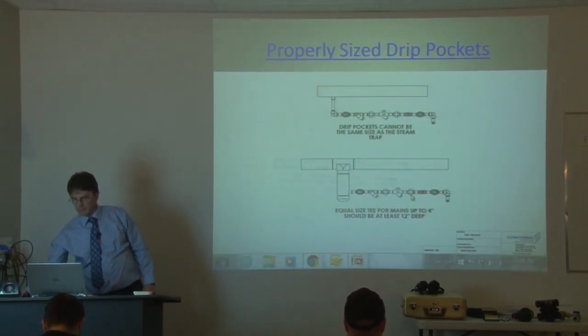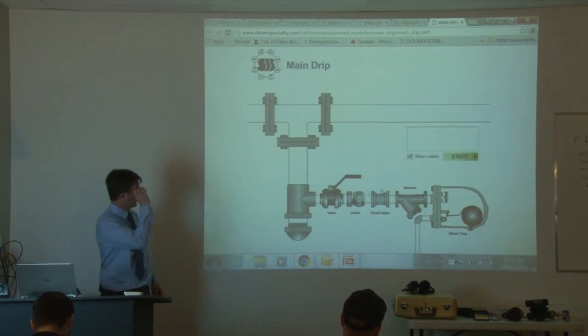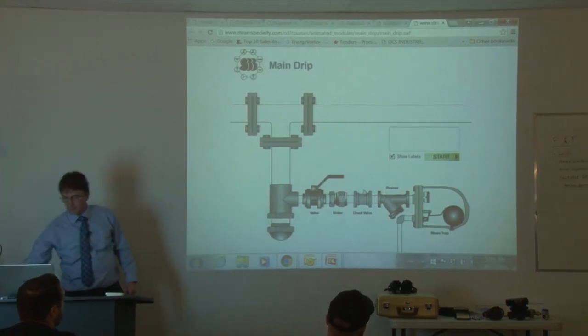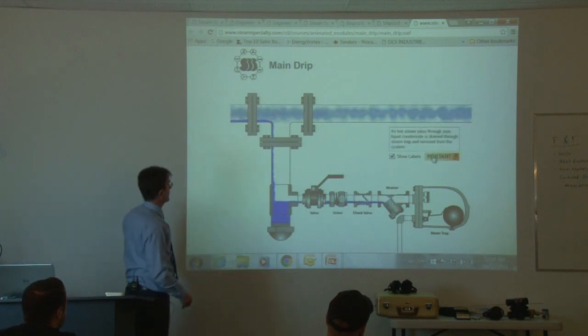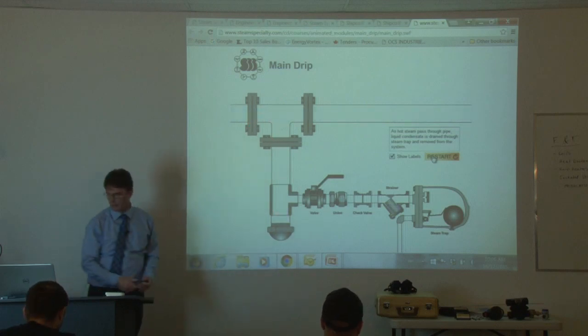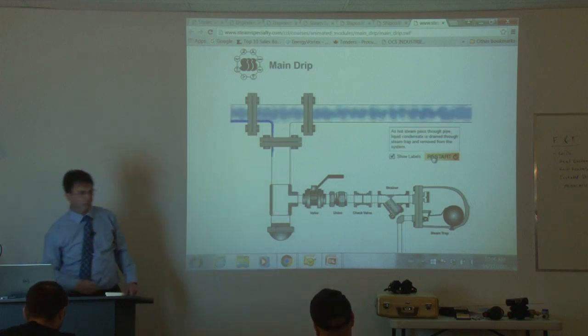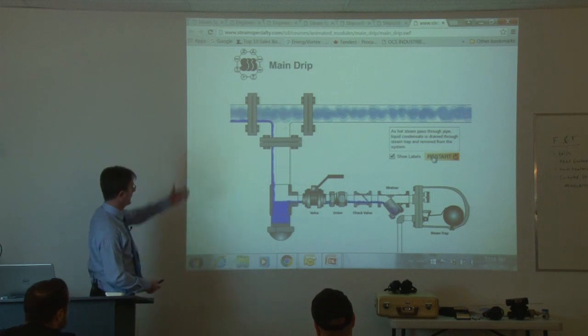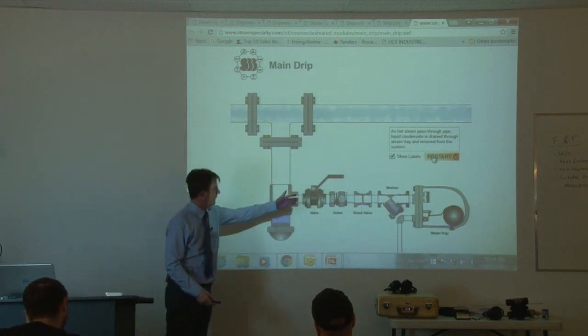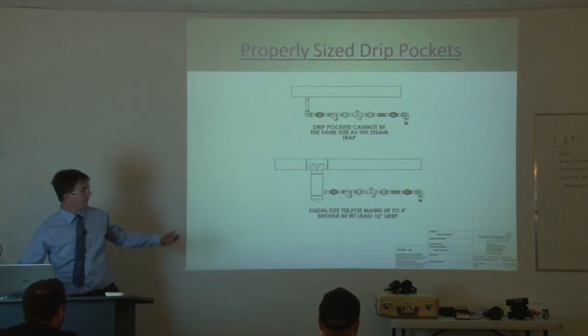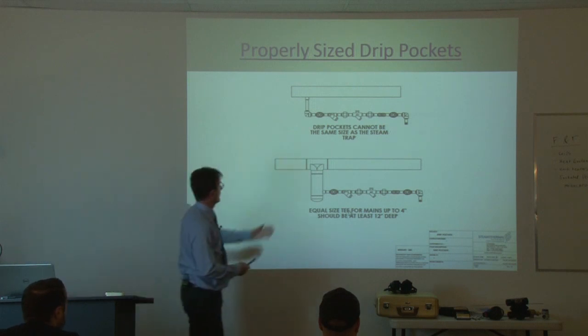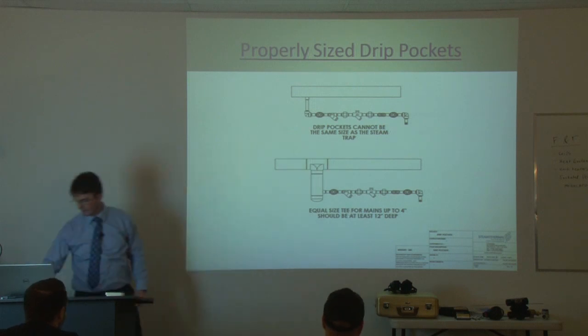So this is another link back to our website. And it shows you graphically why for pipe sizes up to 4 inch, we like to see equal size drip pockets. So having a big enough opening allows the condensate to, went by pretty fast, it allows the condensate to collect and helps the trap operate. Because otherwise, the condensate will just fly over top. So that's why when I'm doing these trap audits, I'm looking for things like this. Just best piping practices.